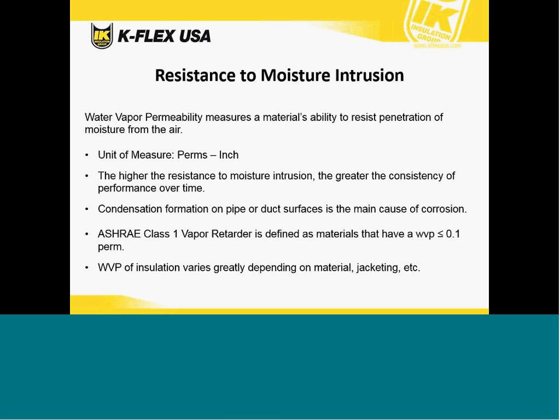Resistance to moisture intrusion is so important in your insulation system. Water vapor permeability measures a material's ability to resist penetration of moisture from the air. These are perm-inches, or for very thin materials, it's generally just referred to as perms. The higher the resistance to moisture intrusion, the greater the consistency of performance over time. As we just saw in the previous slide, over time moisture does introduce itself to an insulation system and the performance will go down. We want to keep it dry to keep that performance stable.